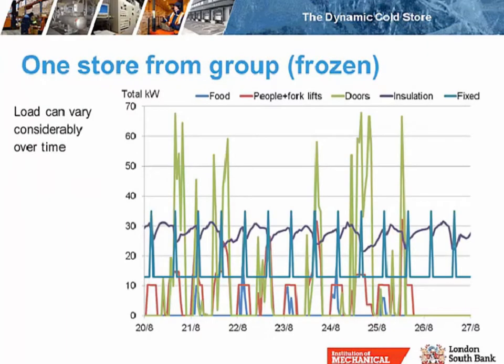Heat loads can also vary over time. The graph I showed before was an average over a long period, but heat loads can vary over a daily cycle — for example in terms of insulation — and the heat load from doors varies quite considerably. You need to take this into account and align your technology to certain times of the day. You really need to understand the heat loads in your cold store to be able to apply the very best technology.